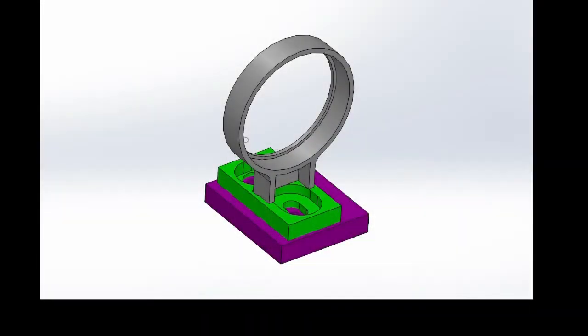But what we don't want is we don't want the blue part being a little out of collimation, and we don't want the red part being a little bit out of collimation. And that results in having an out of focus collimating lens. So in order to help mitigate that, what we did is we added a little cam that moves our collimating lens about a millimeter and a half, and that compensates for the very extreme temperature swings that we can see.